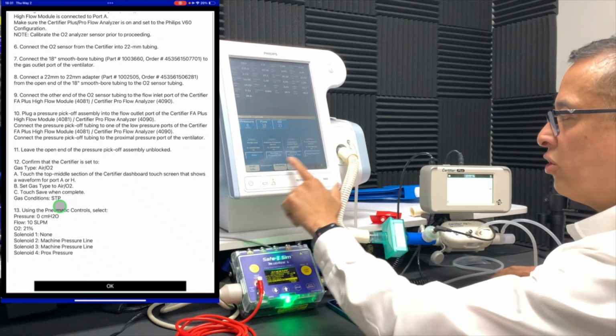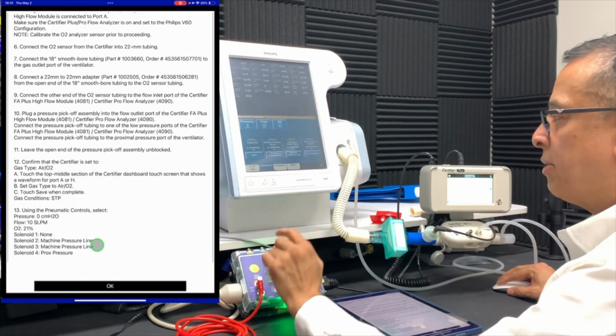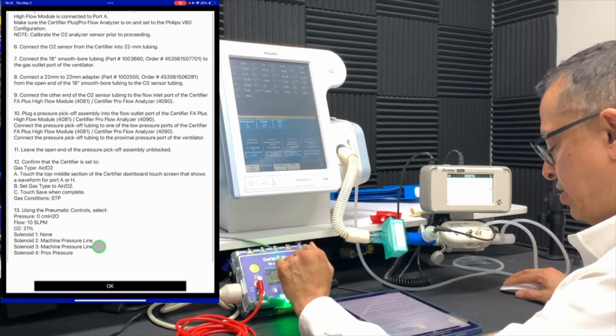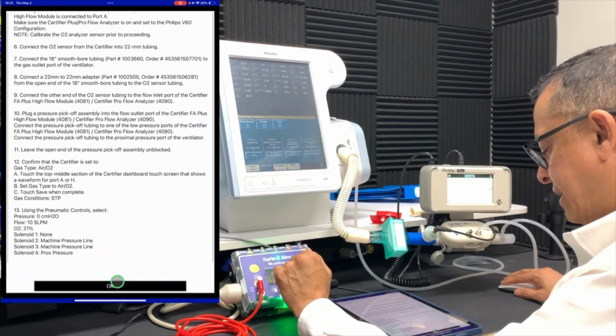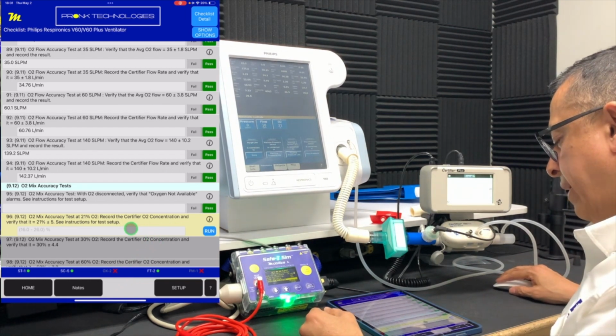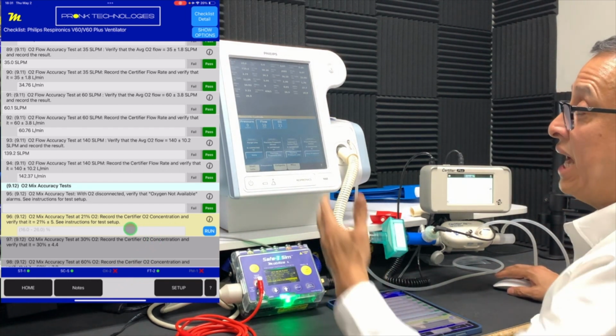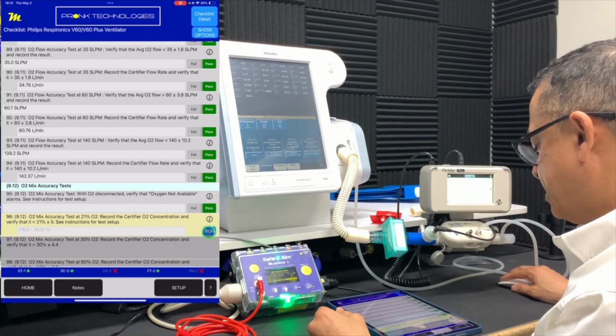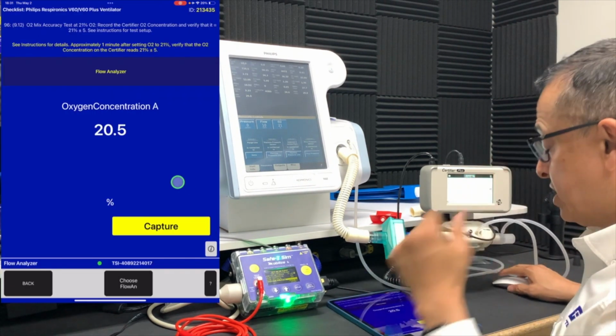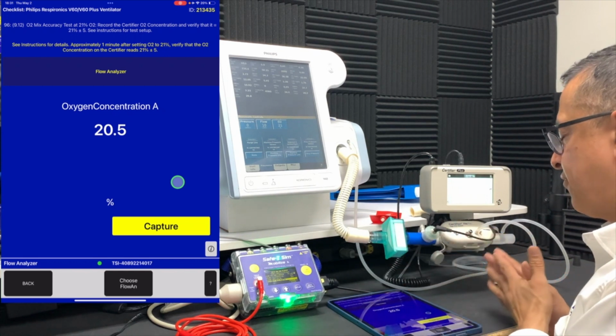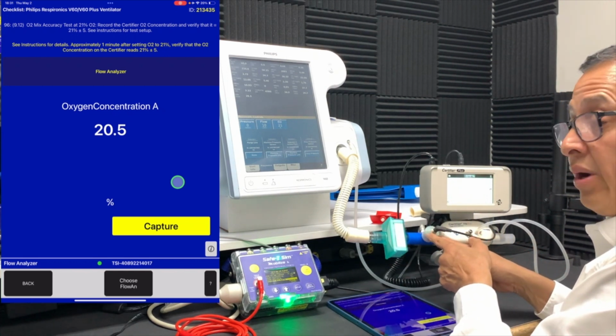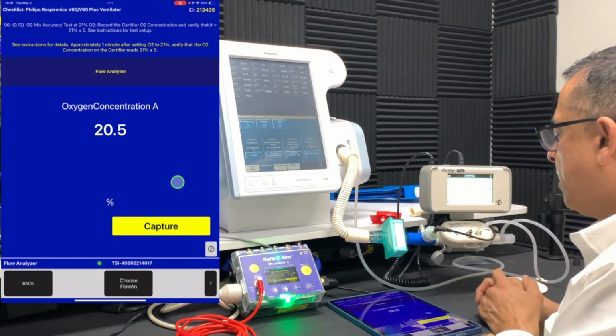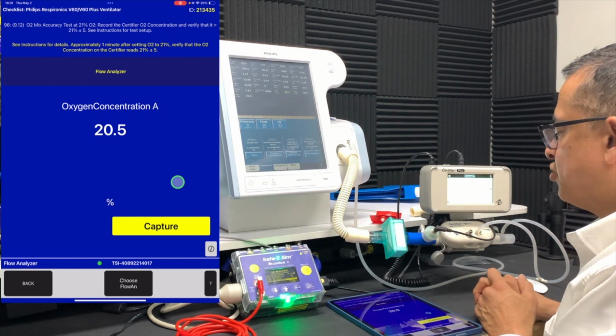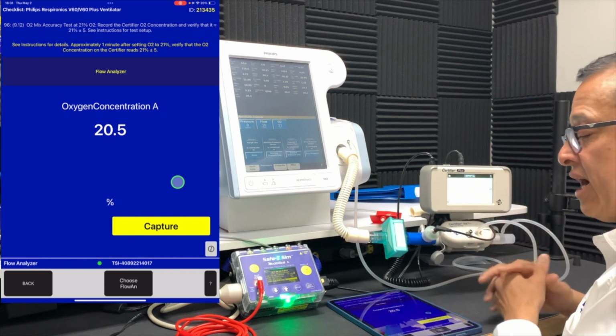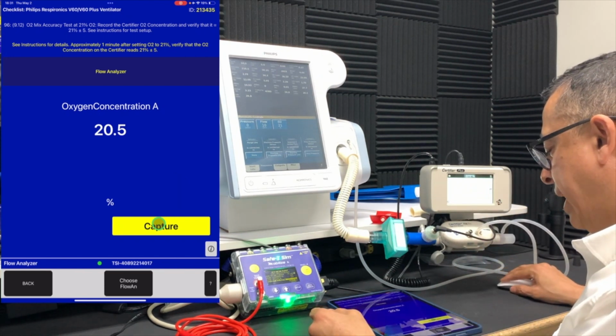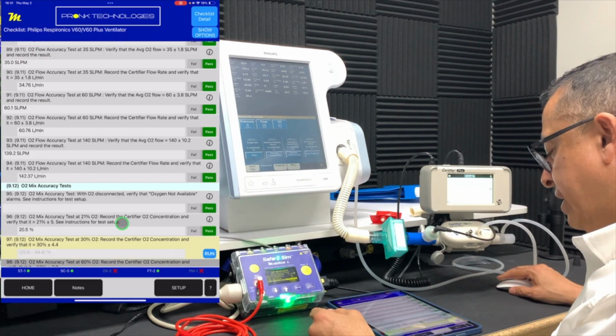Again, you want to confirm your solenoid configuration, which is labeled here at the bottom of the procedure. And we've done that, and it is correct. So we'll go on to the next step. So now we want to see what our O2 mix is at this percentage and make sure that it's correct. So let's see what the concentration value is the certifier measures. So the certifier is measuring this. Of course, you want to make sure you've calibrated your oxygen sensor for the right oxygen concentration. If it's a new sensor, make sure you've done that ahead of time in your analyzer in order to get the accurate measurements. So that's within tolerance here.